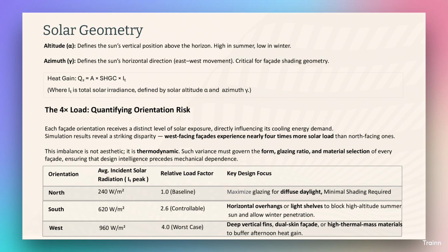Orientation: the 4 times load, quantifying orientation risk. Each facade orientation receives a distinct level of solar exposure, directly influencing its cooling energy demand. Simulation results reveal a striking disparity. West-facing facades experience nearly 4 times more solar load than north-facing ones. This imbalance is not aesthetic, it is thermodynamic. Such variance must govern the form, glazing ratio, and material selection of every facade, ensuring that design intelligence precedes mechanical dependence.